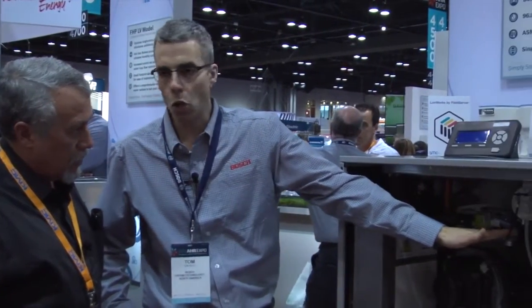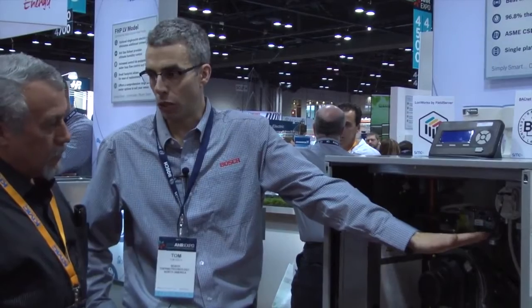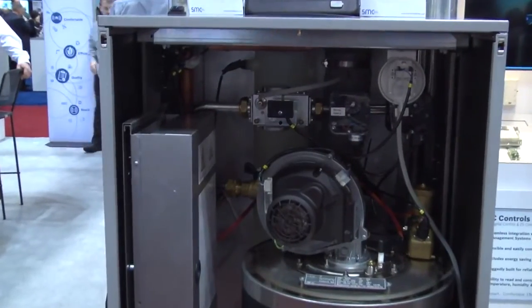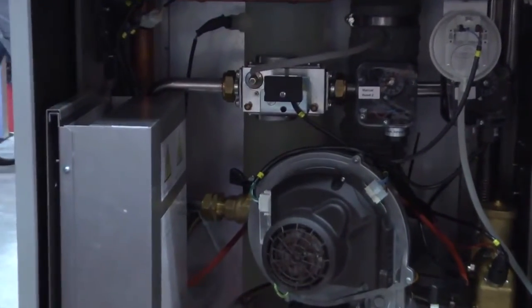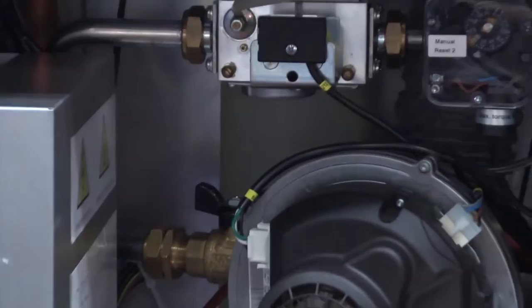And then also the final part of the CSD1 code compliance for commercial boilers is that we have high and low gas pressure limit switches. So we have those built in on our 500,000 BTU boilers and up. And those are tied back to the safeties of the control. So if gas pressure were to go too high or too low, they would also isolate and shut down the boiler. Well, I like the way this is laid out.